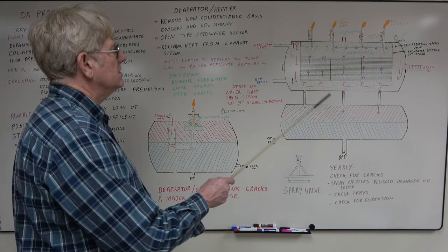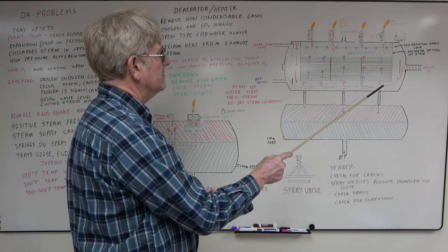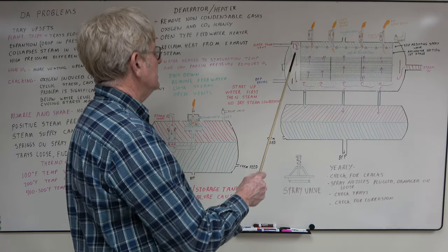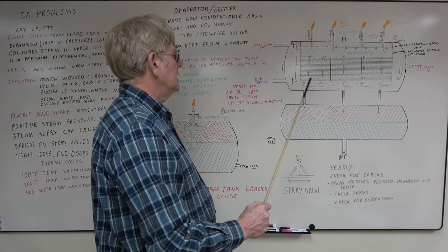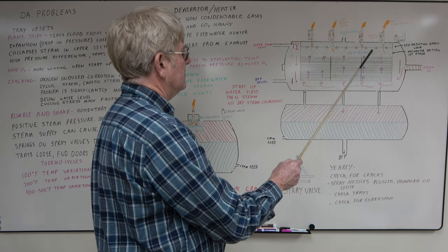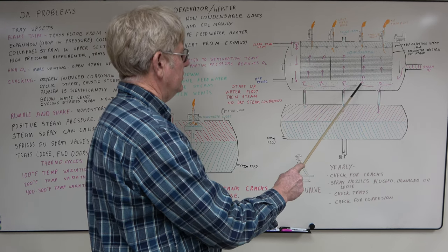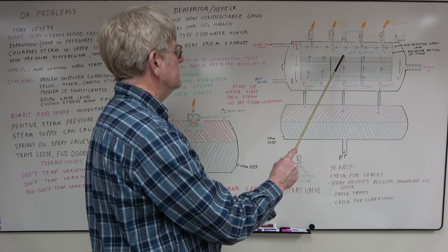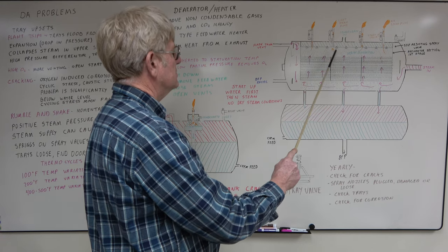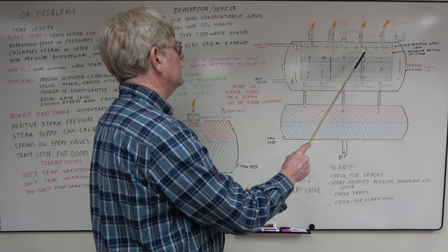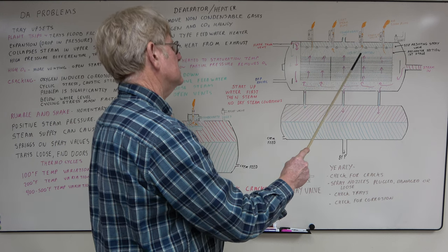This style of deaerator, you have your steam coming in, IP turbine exhaust, you have your flash tank vent dropping in, you have your condensate coming in the top. Your steam comes in, it counter flows. Down here you have very little oxygen in the steam coming up through the trays, and the water is sprayed in. The condensate removes all the oxygen, condenses the steam.